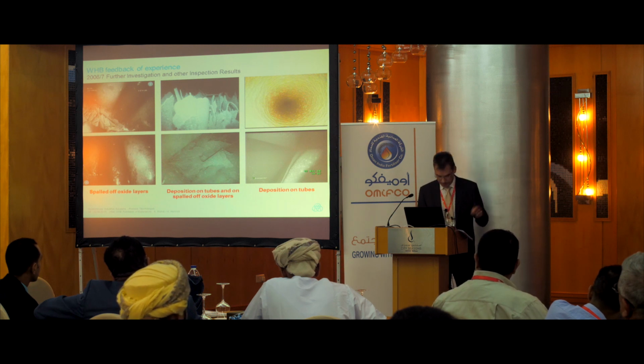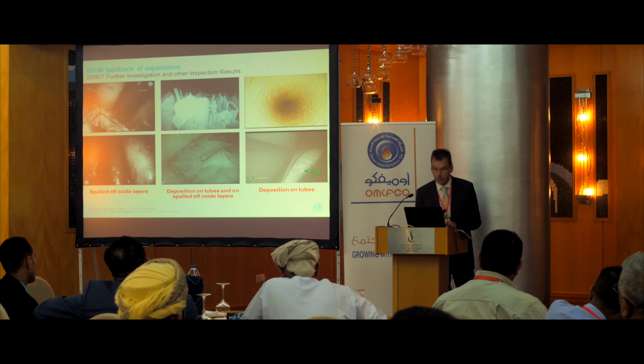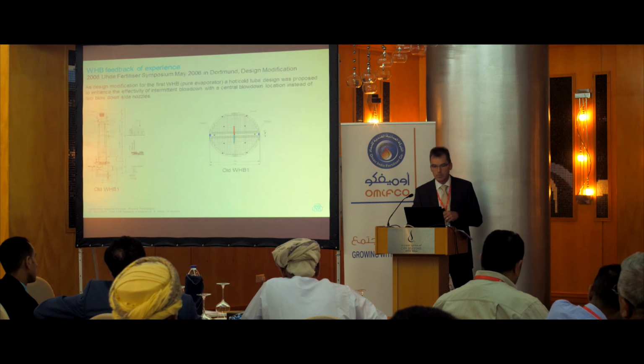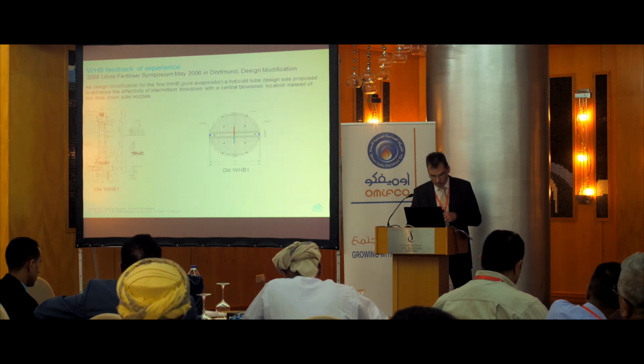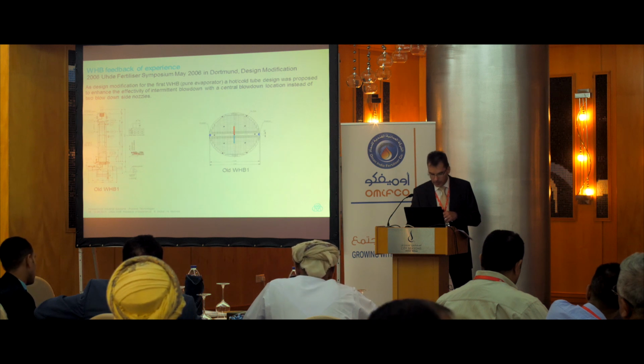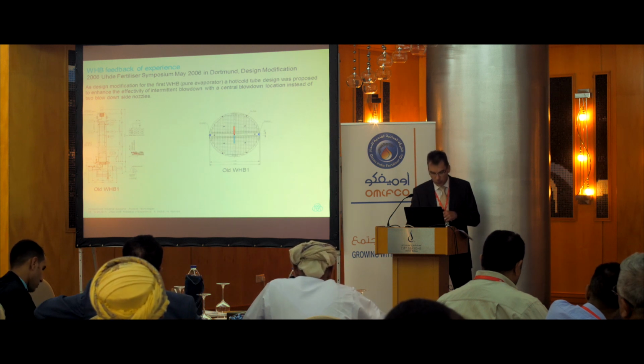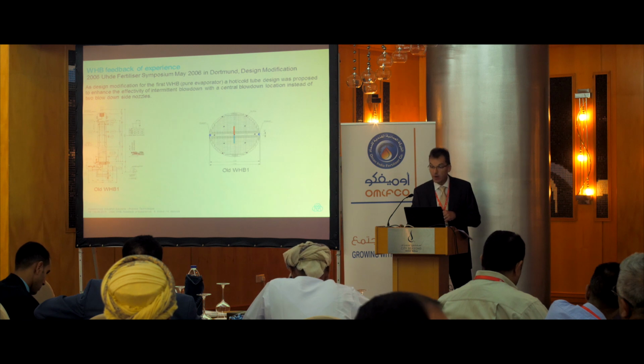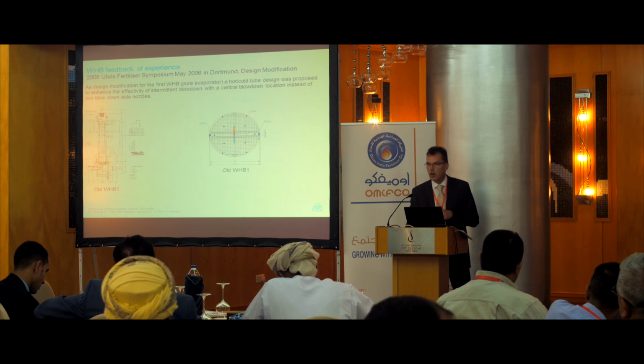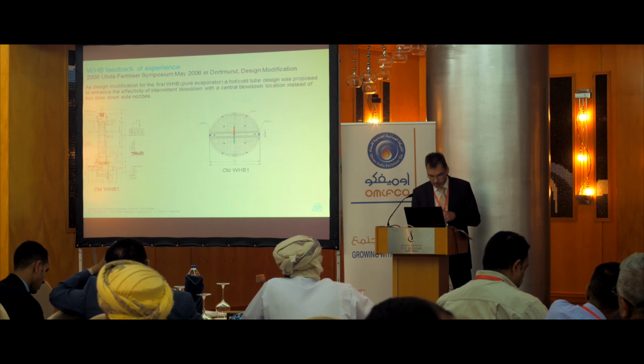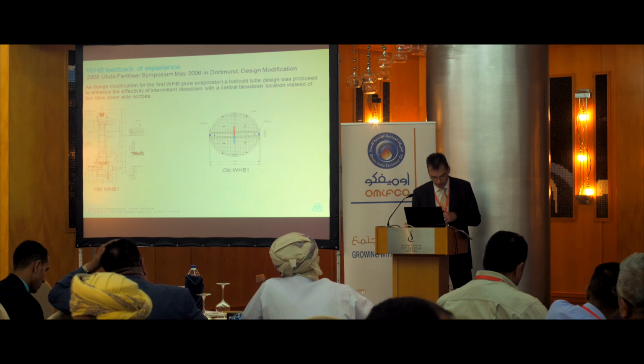Now, what can be done with all these investigations to avoid such depositions inside the boiler? First of all, we made a design change in one of the boilers. As a consequence of the obvious collection of deposits inside the boiler, one of the efforts was to improve the intermittent blowdown. The fountain-type boiler already had a blowdown, as I showed you at the beginning, but the other boiler did not have it.